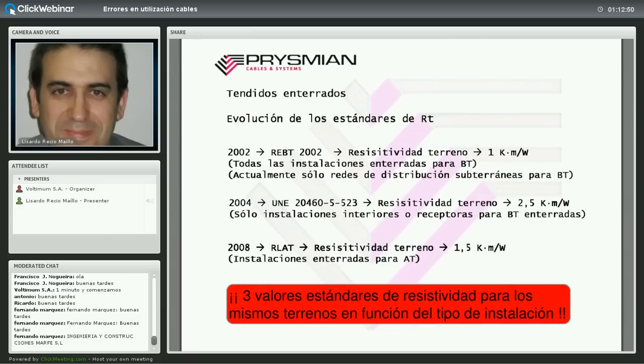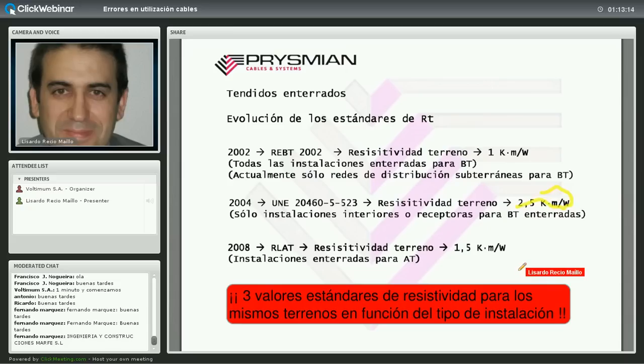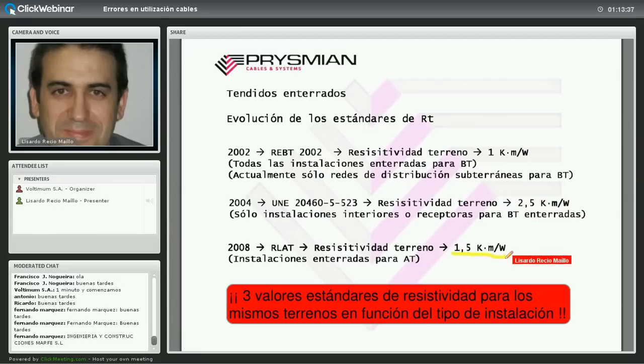Resumiendo: para redes de distribución en baja tensión aplica el reglamento de 2002 con resistividad térmica estándar de 1 K·m/W; para lo que no son redes de distribución en baja tensión aplica la UNE 20460-5-523 con 2,5 K·m/W; y para redes subterráneas de alta tensión (reglamento de 2008, en vigor desde marzo de 2010) la resistividad es 1,5 K·m/W. Tres valores estándares de resistividad para los mismos terrenos según el tipo de instalación.